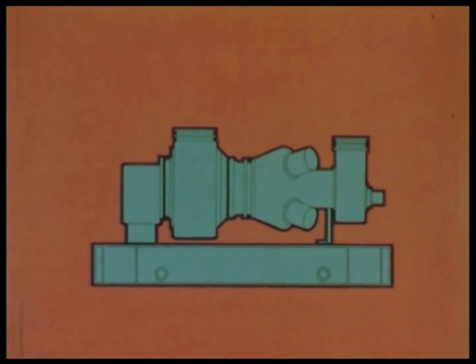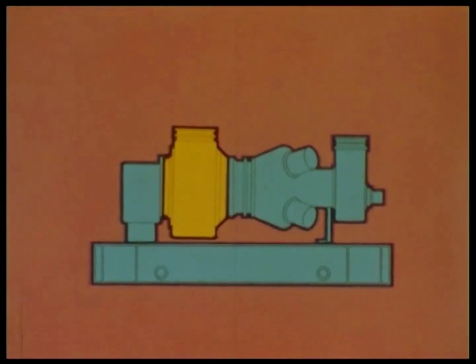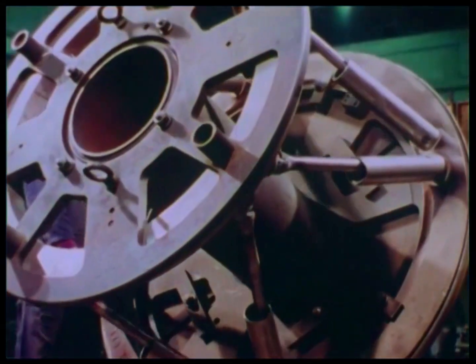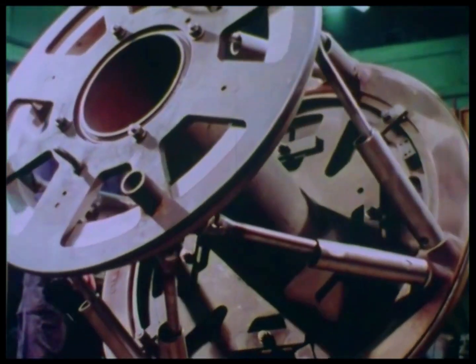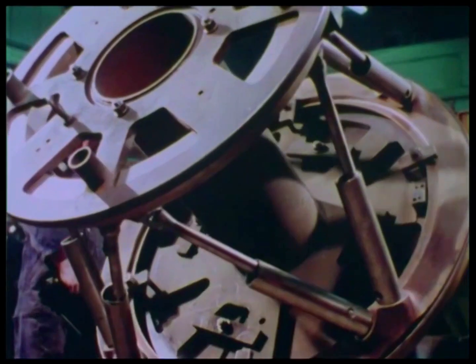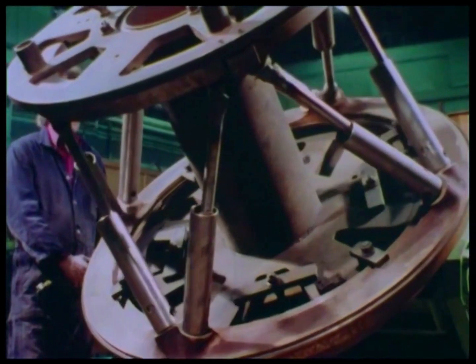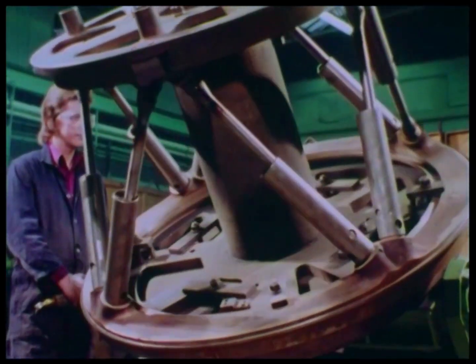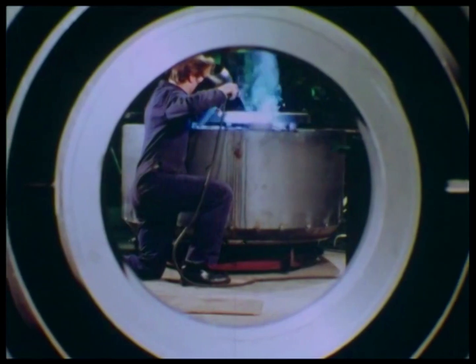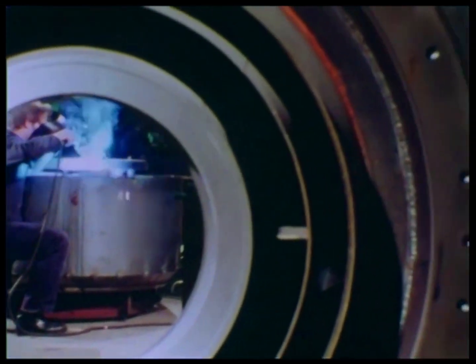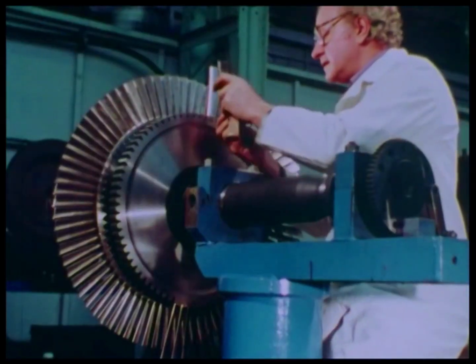Important design features are also incorporated in the power turbine. It is carried from the gearbox by a triangulated tubular structure. Since the struts pass through the exhaust duct, they are encased in tubular outer shields and cooled by air. The whole assembly is designed to be compact and rigid with alignment maintained between static and rotating elements.